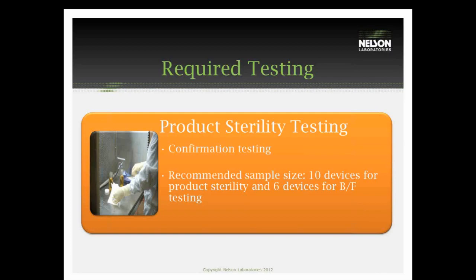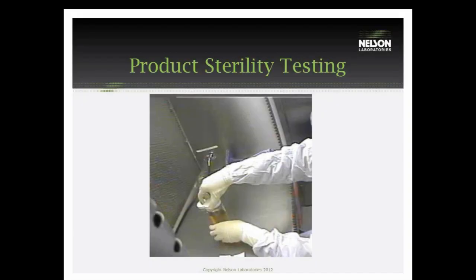Following the half cycle is when we would do the product sterility testing. This testing is confirmation testing and does not go towards clearing your devices as sterile. It just confirms that during the half cycle, the dwell time, concentration, and temperature exceeded the necessary requirements for the natural bioburden on the products. For this testing we recommend ten devices for product sterility and six devices for bacteriostasis/fungistasis testing. The bacteriostasis/fungistasis testing, or BF testing, is a necessary test to validate the product sterility results.